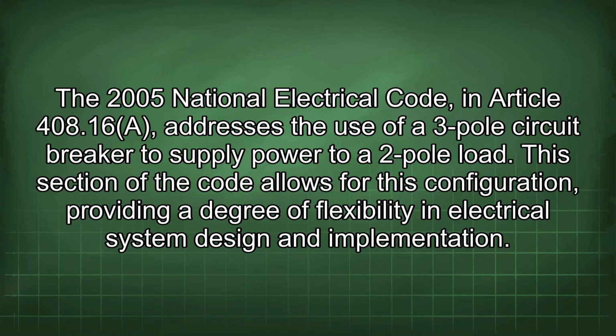The 2005 National Electrical Code, in Article 408.16(A), addresses the use of a 3-pole circuit breaker to supply power to a 2-pole load. This section of the code allows for this configuration, providing a degree of flexibility in electrical system design and implementation.